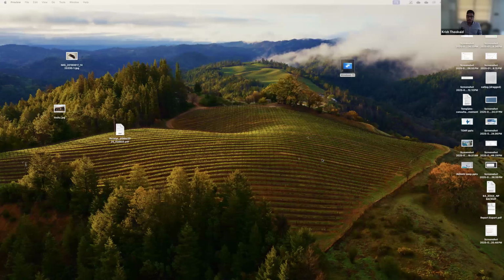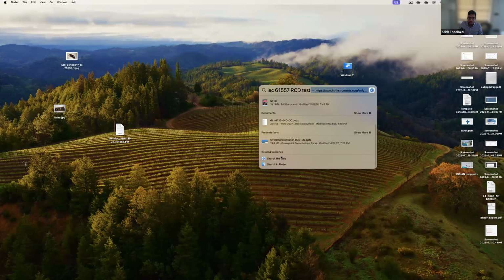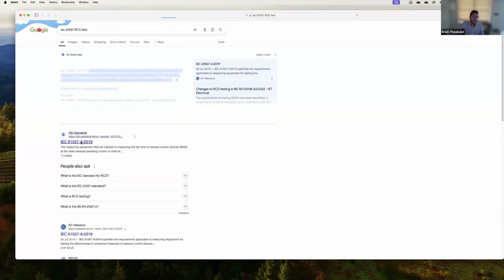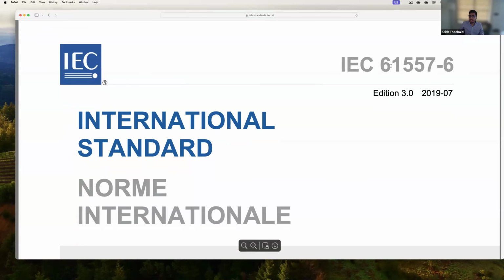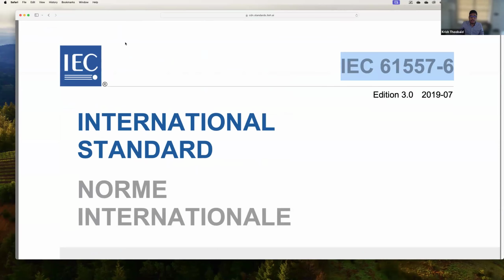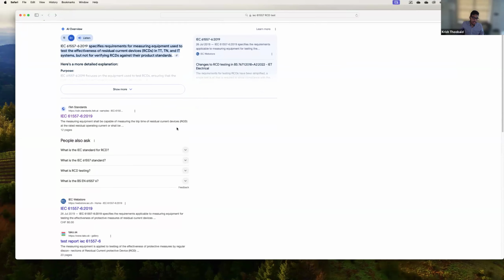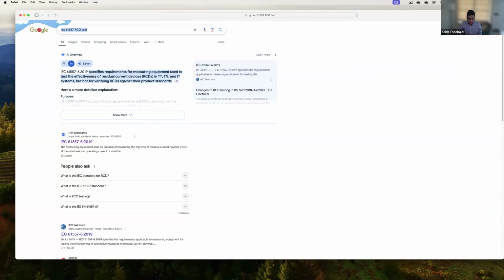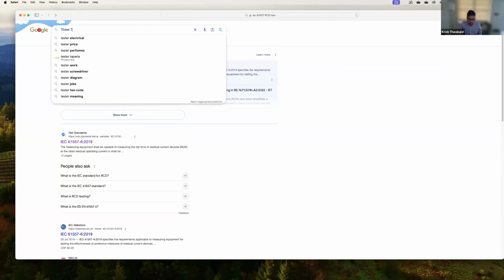Yeah, I will answer the first question regarding whether there is a standard way to test. Absolutely, there is a standard way to test. You have to get a test instrument that conforms to a particular standard. I will just show you. If I just search for IEC 61557-6, this is the standard that talks about test equipment that can test an RCD. There are a variety of devices.